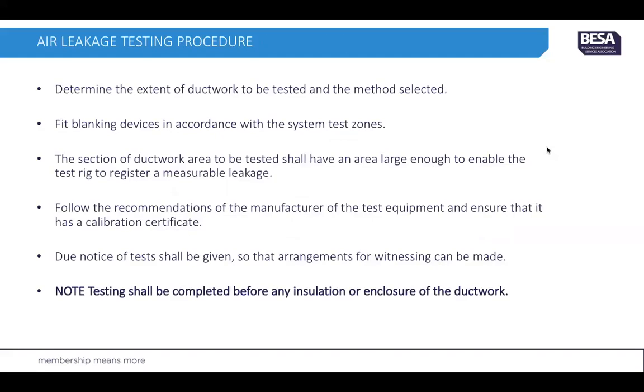For the air leakage testing procedure, you need to determine the extent of the ductwork to be tested and the method selected. Fit the blanking devices in accordance with the system test zones. The section of ductwork to be tested shall have a large enough area to enable the test rig to measure a measurable leakage — a small amount of ductwork is sometimes not large enough for the test machine. You need to follow the recommendations of the manufacturer of the test equipment.